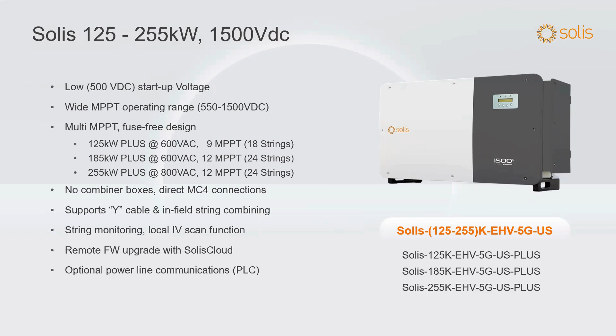You can set up these systems with power line communications. We have a small box that can convert - these inverters come with a PLC transmitter board in them. Although there are many ways to connect to the communication board inside the inverter, you may want to save money and not run any communication lines at all, and instead transfer the data via PLC. We have a small box installed near the point of common coupling that takes those PLC signals and converts them back to RS-485. Just another way to save a little money on these systems.